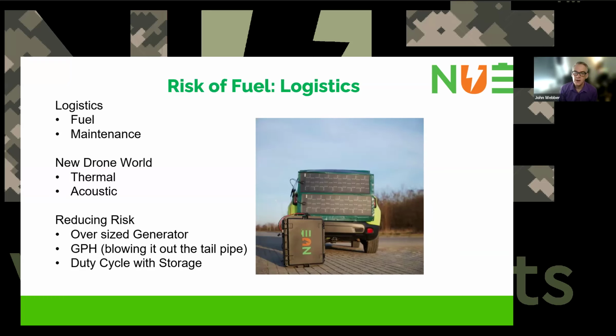One of the other risks we've seen, not only in the military but on the disaster side as well, is oftentimes you'll see 3 laptops being run by a 5, 10, or 20 kW generator—10,000 watts of capability running 250 watts of load with a couple laptops and a Starlink. That's a huge waste of fuel.